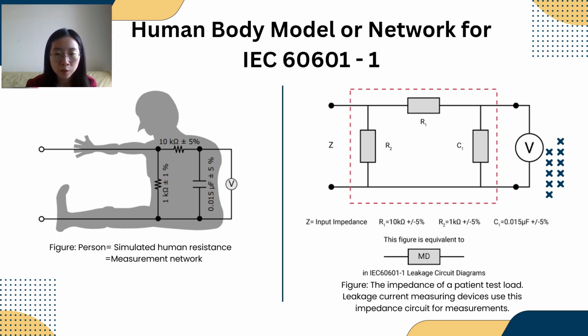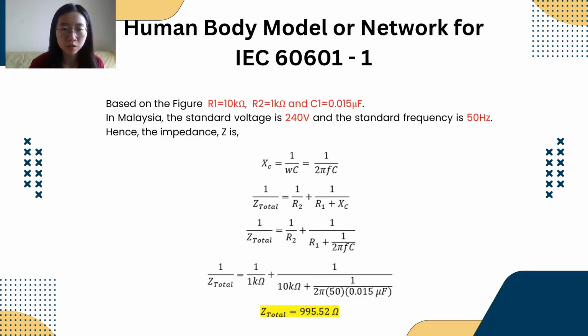This figure is equivalent to the measuring device in the IEC 60601 leakage circuit diagram. Based on the figure just now, R1 is 10 kilo ohm, R2 is 1 kilo ohm, and C1 is 0.015 microfarad. In Malaysia, the standard voltage is 240 volt, and the standard frequency is 50 Hz. Hence, we can calculate the impedance Z as below. We get Z total equal to 995.52 ohm.